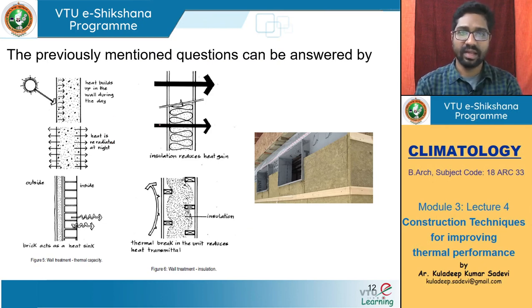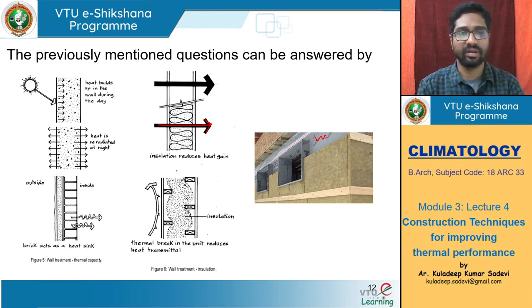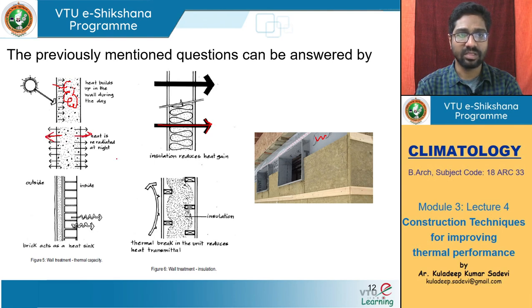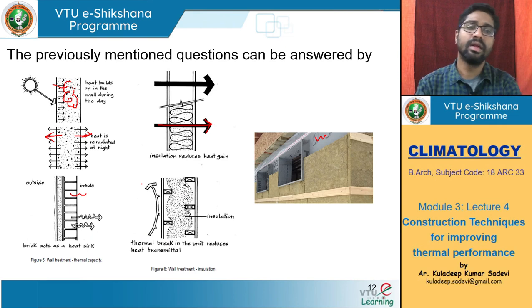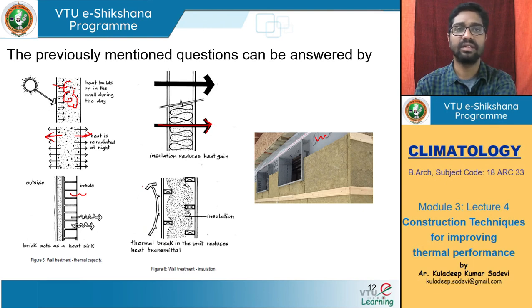By adding insulation, heat gain is reduced. You have a wall, you put insulation, fix it with boards, and have your final facade treatment. Brick acts as a heat sink here — in the daytime, heat gets into the wall and is stored; in the night, it dissipates on both sides toward outside and inside. The moment you have insulation on the outside, the wall starts giving heat only to the indoors. Having battens and putting insulation outside will stop heat from entering the structure itself. Whether to place insulation inside or outside depends on your thermal comfort requirements.